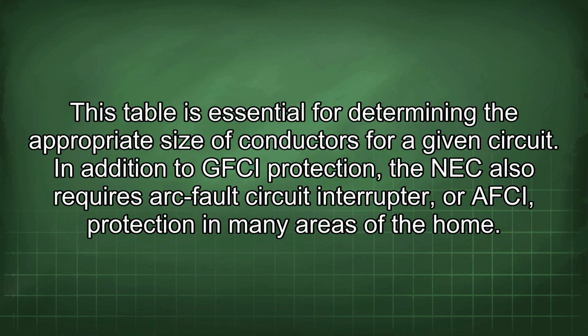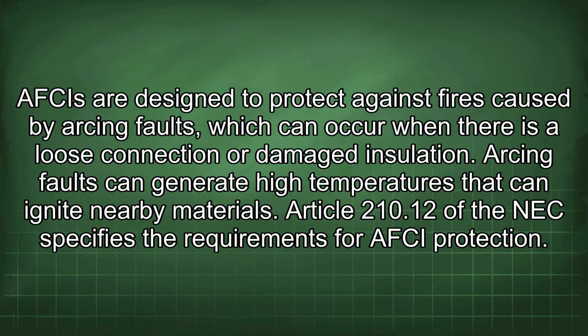In addition to GFCI protection, the NEC also requires arc fault circuit interrupter, or AFCI, protection in many areas of the home. AFCIs are designed to protect against fires caused by arcing faults, which can occur when there is a loose connection or damaged insulation. Arcing faults can generate high temperatures that can ignite nearby materials. Article 210.12 of the NEC specifies the requirements for AFCI protection.